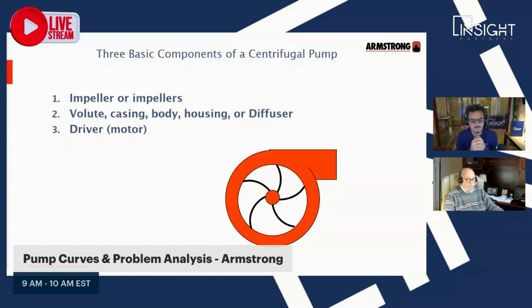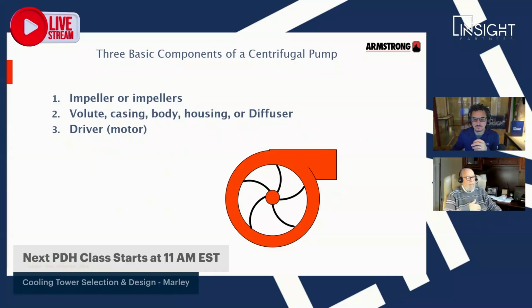And then we have a driver. Now, we're not going to talk about whether it's constant speed or variable speed, and whether you have a starter or a variable speed drive on it, because that doesn't affect the pump construction in and of itself. All pumps have the same basic component parts. You have to understand those parts are fixed by us as pump manufacturers. We decide what size the casing has to be, what size the impeller has to be, to optimize motor horsepower to the flow and head that you as the engineer need for your system.